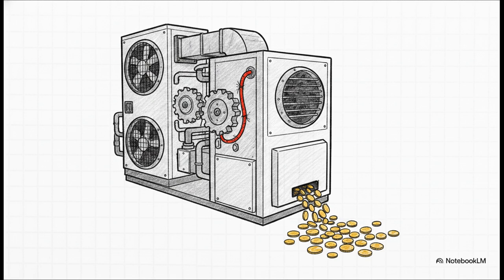We're talking dirty coils, improper operating schedules running the AC at midnight, faulty temperature sensors, or failed economizers. And economizers, by the way, are just the mechanical dampers that are supposed to open and bring in free outside cooling when the weather is nice. You might even have systems that are simultaneously heating and cooling at the exact same time, literally fighting each other. The equipment just keeps running, but your efficiency is silently bleeding away.